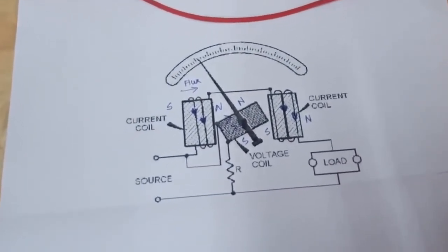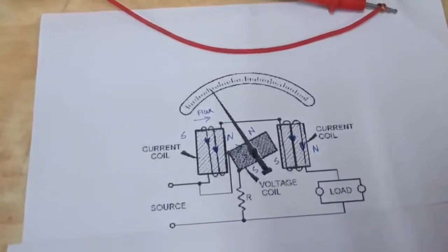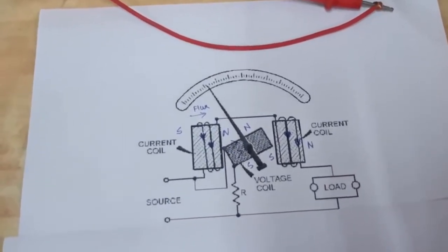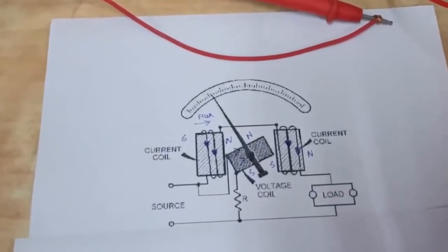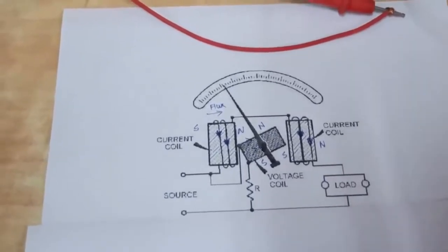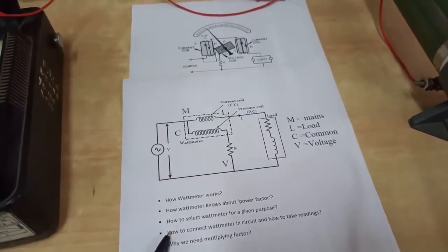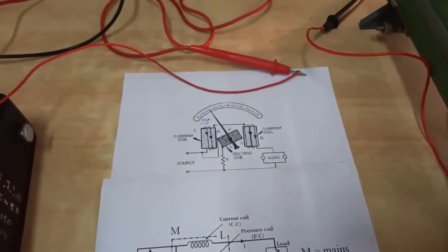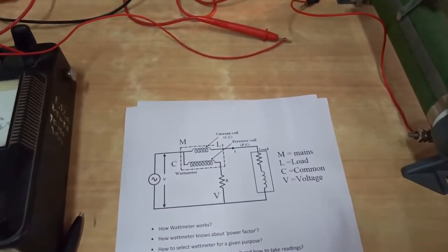For a reactive load like an inductive load, for half of the time the two currents are in different directions and for half the time they are in the same direction. Their resultant deflection will be zero because they rotate in opposite directions for equal time with equal strength. This is how the wattmeter accounts for power factor — it doesn't measure power factor directly, it actually measures the average value of power.